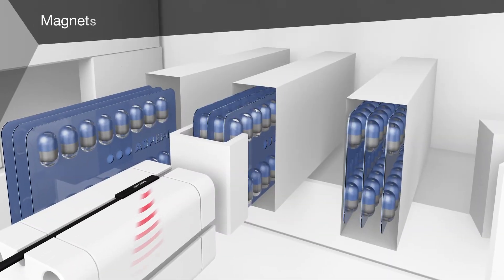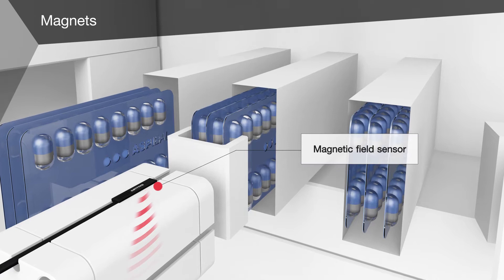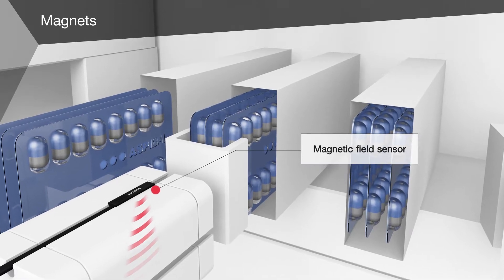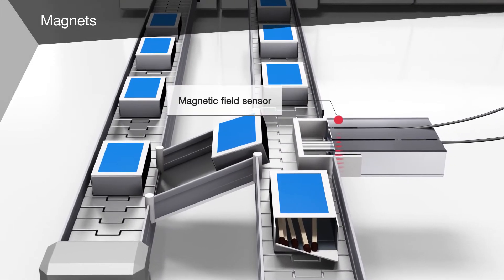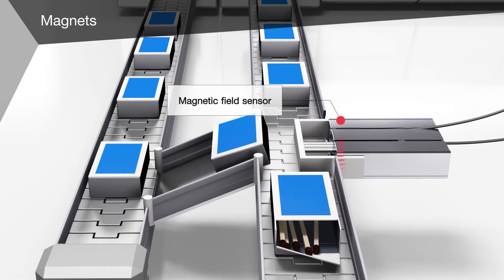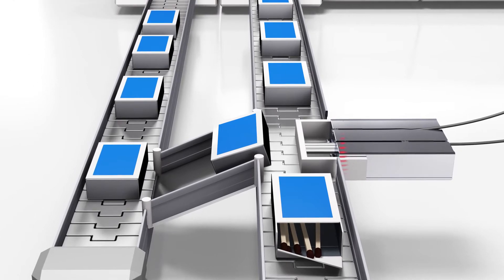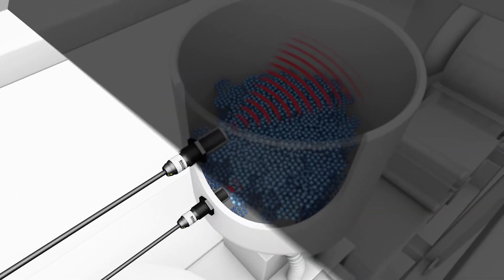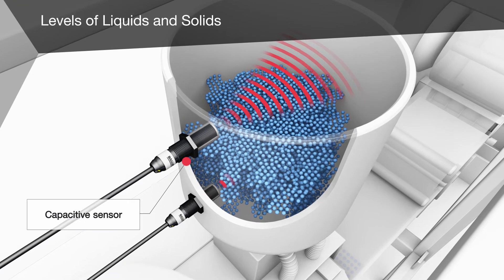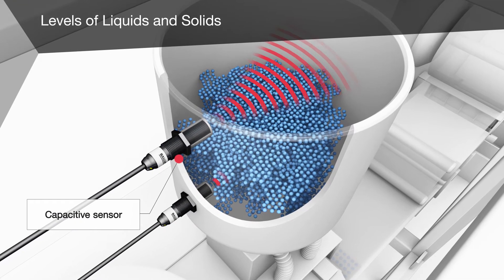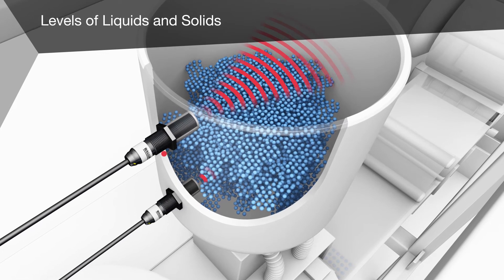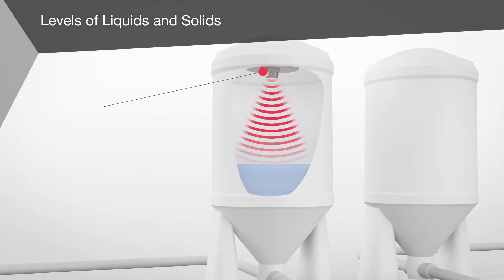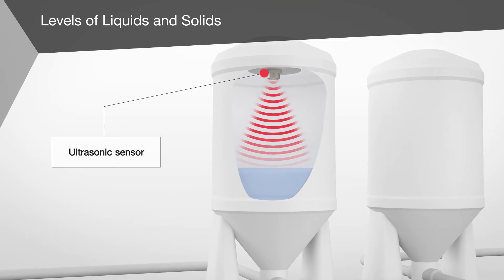Magnetic field sensors are used to detect magnets for piston position monitoring. Here, for example, they detect the position of the gripper when feeding blister packs, or the position of the matchbox ejector. Detection of fluid and solid levels is performed, for example, by capacitive sensors such as point level monitoring of plastic granulate, or ultrasonic sensors used here to check the fill height in tanks.